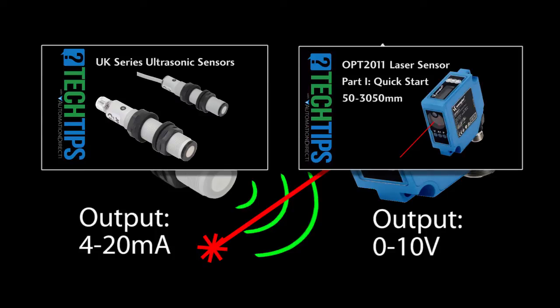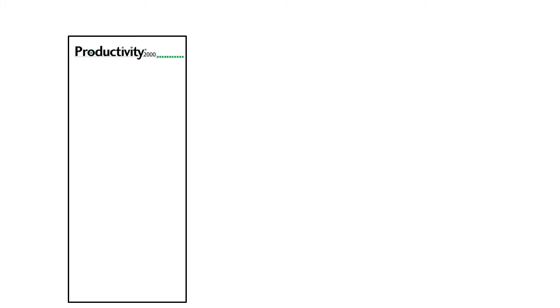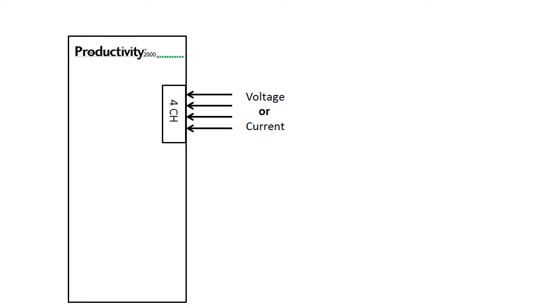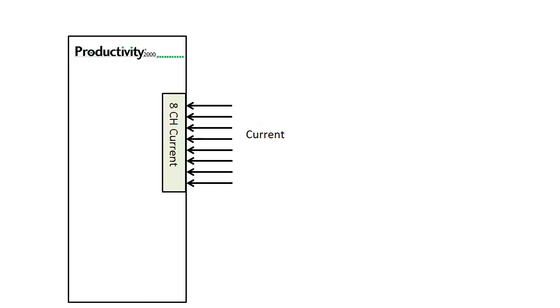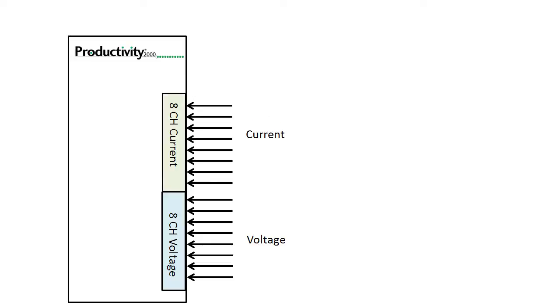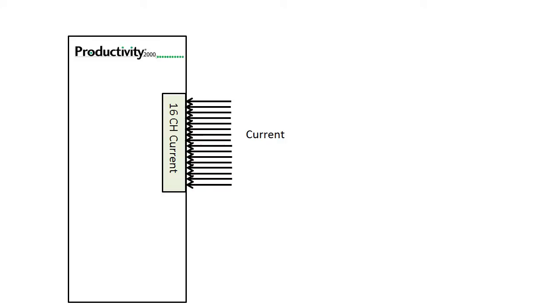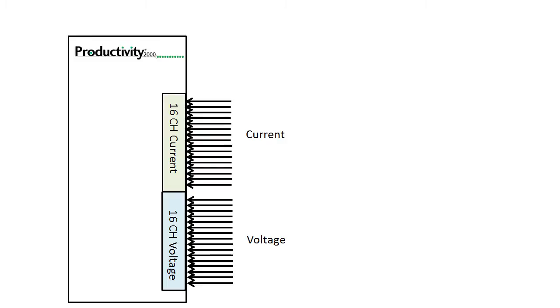We just take those outputs and wire them into the analog inputs of the controller. The Productivity 2000 has several ways we could approach this. We could use a single 4 channel input module that can do voltage or current, an 8 channel current input module and an 8 channel voltage input module, or a 16 input current module and a 16 input voltage module.